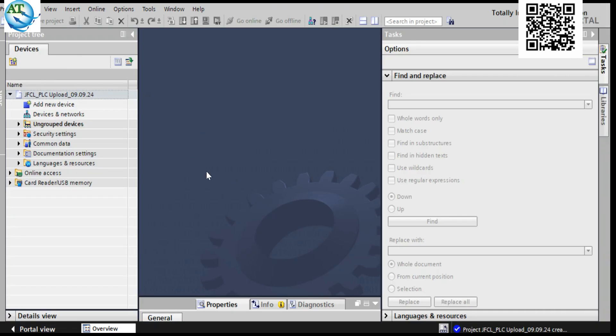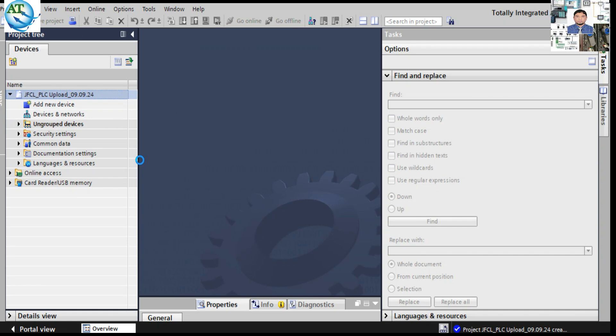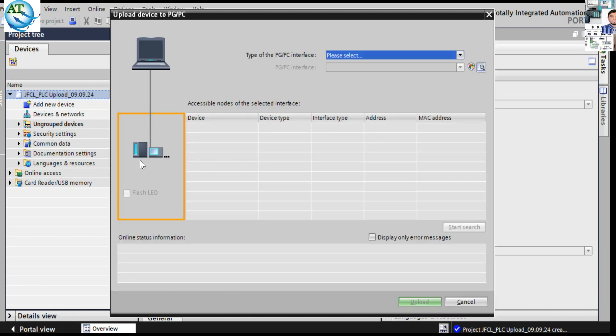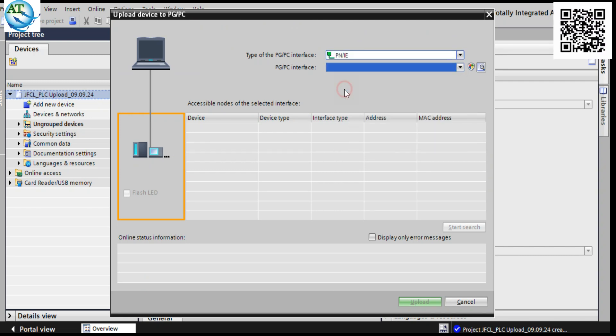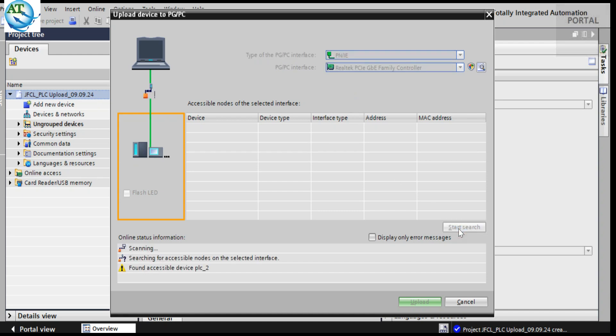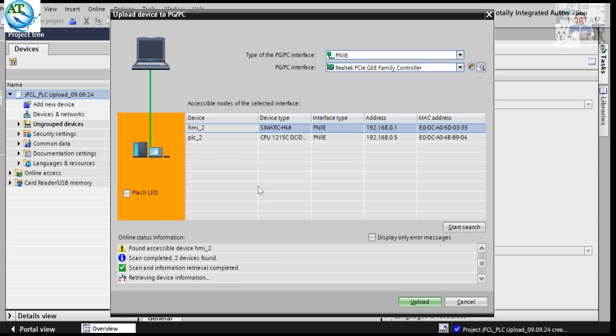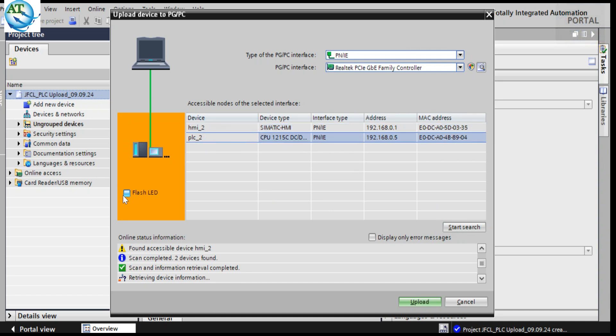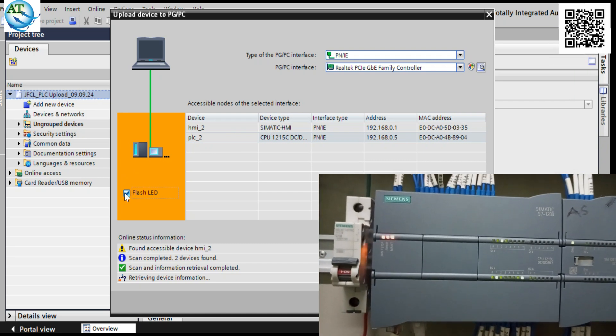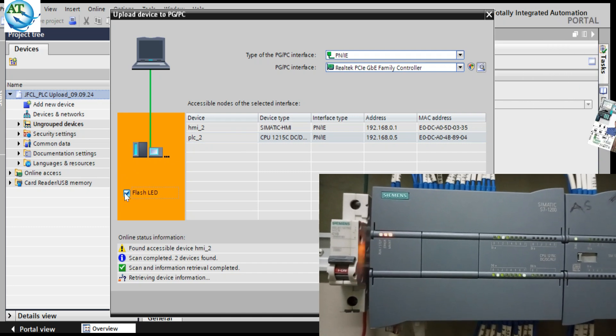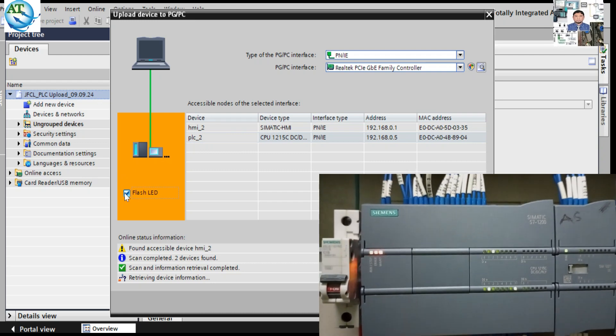Then we select the PLC by the project name, then you can go to online. You can see 'upload program from device' — upload program from PLC. Then you can select the connection cable; it is the PN interface. Then you can see the PG/PC interface — select the first one. Then press Start Search. Here you can see all connected devices showing in this program on this cable — you can see the HMI and PLC. We want to upload the PLC program. So you can check the connection is okay by pressing the Flash LED. You can see on the right-hand side that the PLC is flashing, which means the communication is complete — 100% communicated with the PLC.